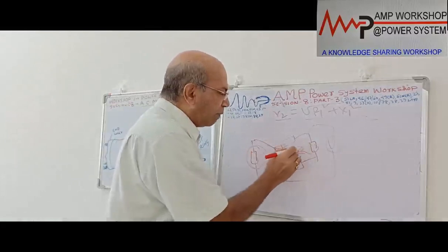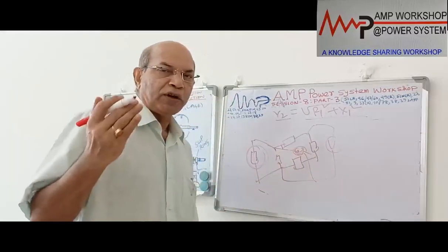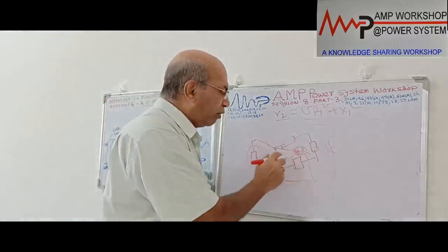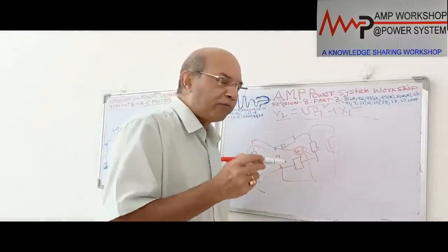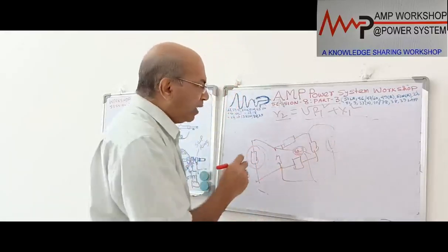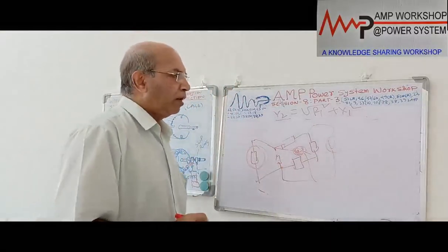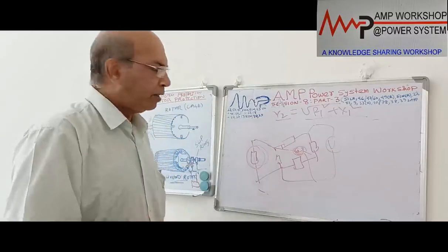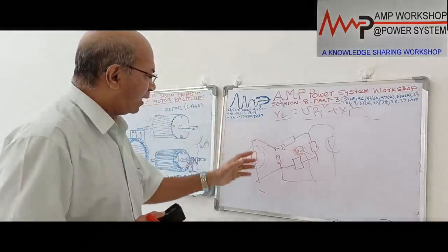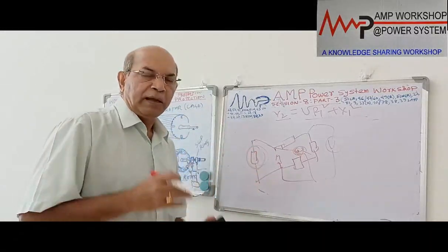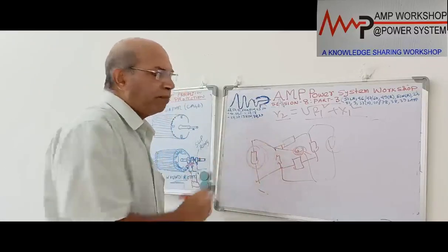With this magnitude, in place of the ammeter needle we can put a strip chart recorder which has a contact on the back side. That recorder will represent the rotor temperature or rotor resistance value, and from the recorder we can take the alarm or trip contact. In this way, in case of a wound rotor, we can monitor the winding temperature. We can put this arrangement in a synchronous motor also, if the synchronous motor has a slip ring arrangement. In that case also, we can monitor the rotor resistance or rotor temperature.